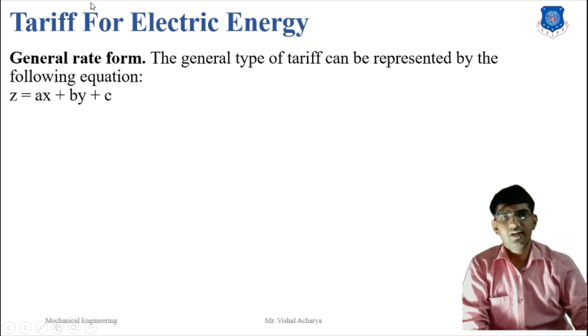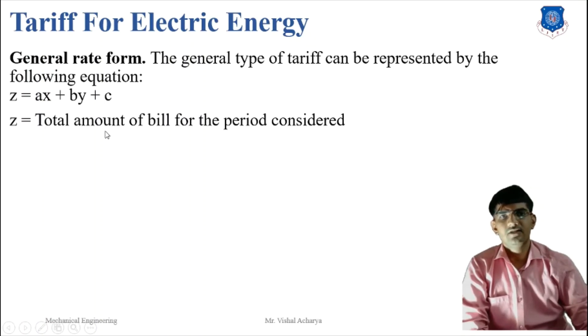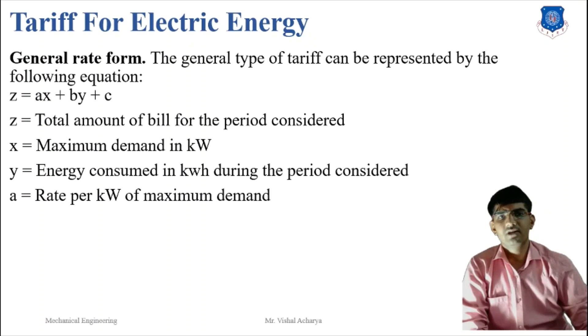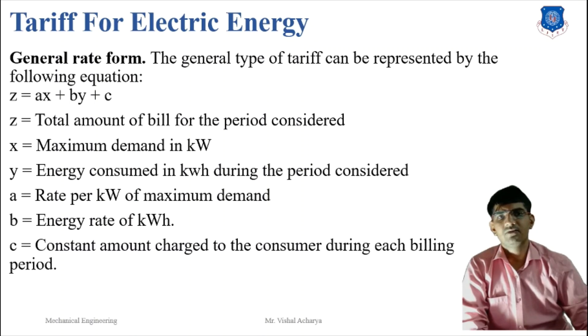Here is the general rate form. The general type of tariff can be represented by the equation: Z = AX + BY + C. Here Z is the total amount of bill for the period considered. X is the maximum demand in kilowatts. Y is the energy consumed in kilowatt-hours during the period. A is the rate per kilowatt of maximum demand. B is the energy rate per kilowatt-hour. C is the constant amount charged to the consumer during each billing period.